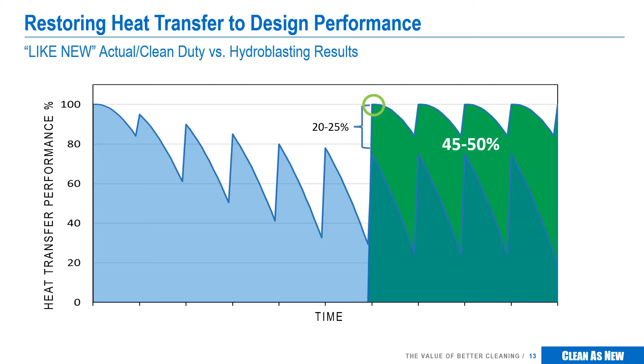There's another benefit that this simulation highlights. By using the same fouling level as the trigger to clean the bundle, rather than the same fixed interval, better cleaning offers the opportunity to more than double the run length, reducing maintenance costs and improving production, while still reducing overall energy consumption.